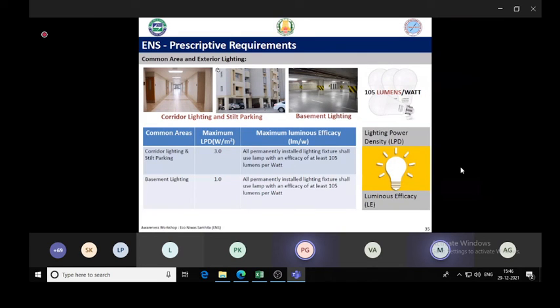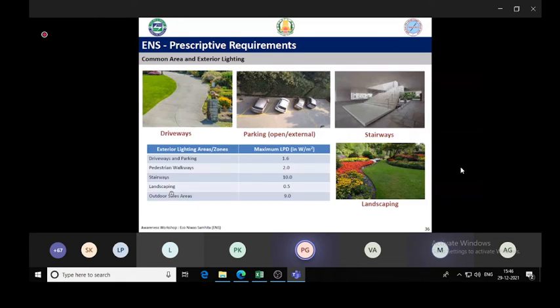For example, here the common area and exterior lighting, the LPD should be less than 3 for corridor lighting, and for basement it should be less than 1 watt per meter square. And the luminous efficacy, otherwise, it should be more than 105 lumens per watt. So basically your LED lighting, generally it's more than 100. And LPD also can be complied with when you use LED light without excessive lighting. If you are designing with excessive lighting, then again you cannot comply. Similarly, for other open areas like driveways, again there are LPD requirements in the code. Driveways, stairways, landscaping area, these are to be complied with.